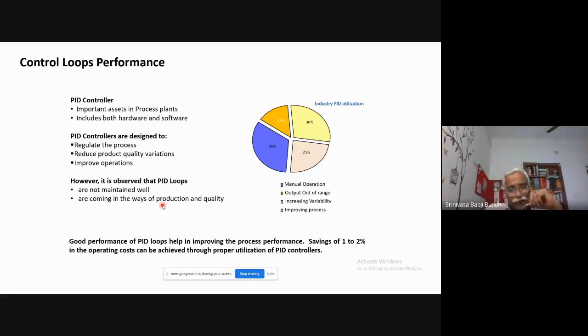Okay, several industrial studies have been carried out, and what they found is shown in this pie chart. They found that only about 25% of the loops are working properly. That means they are able to regulate the process properly. The remaining loops are having issues like manual operation. Many times when you go to the plant, collect the data, and do the analysis, you find that almost 30-35 percent of the loops are operating in manual. Then about 15 to 20% of the loops, you'll find them as output out of range. That means they are in saturated conditions. That means the output is either at the maximum limit or the minimum limit.